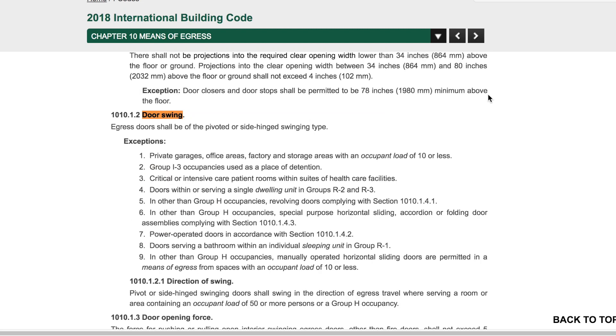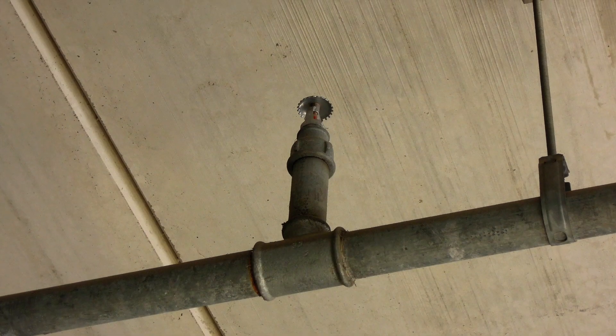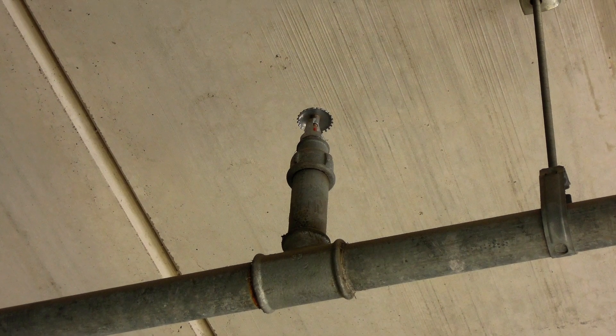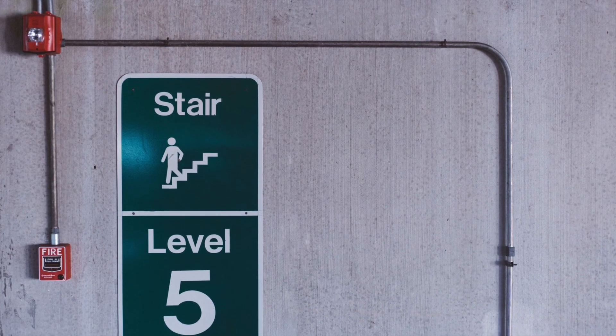In high hazard occupancies, and in all other occupancies where the occupant load of the space is 50 or more, the door also must swing in the direction of exit travel. Occupant loads above certain capacities may also trigger life safety and fire protection requirements, such as requirements for automatic sprinklers and fire alarm systems.